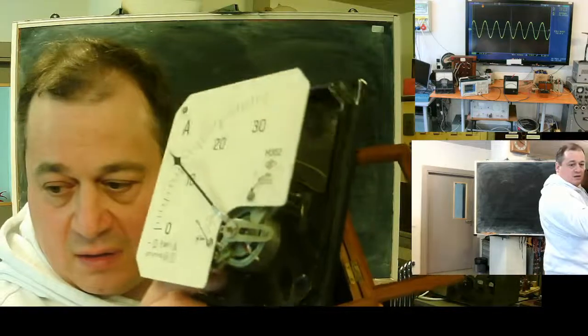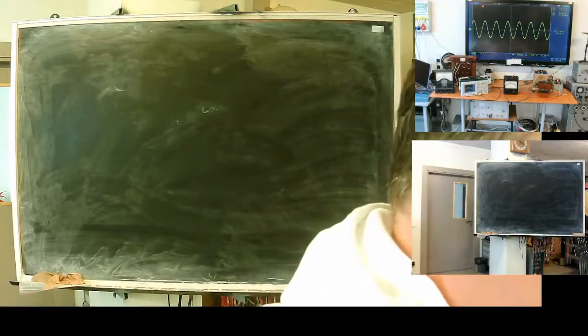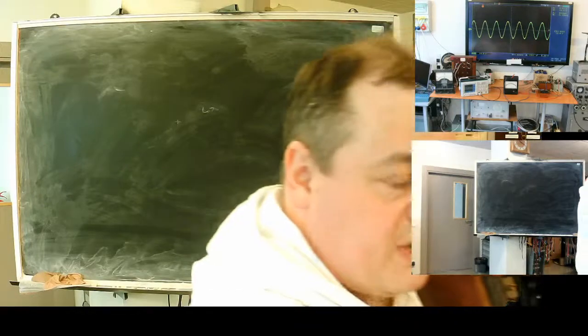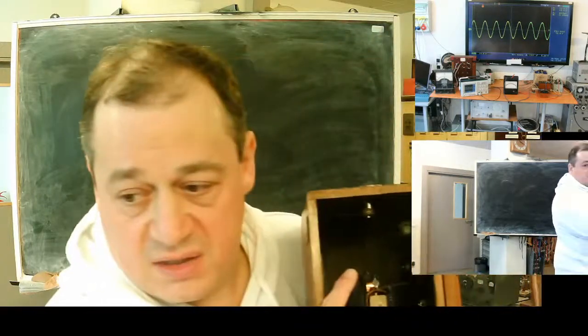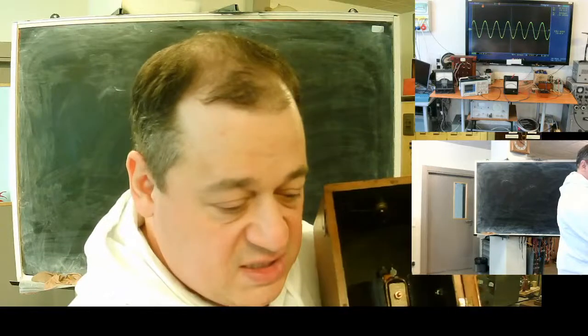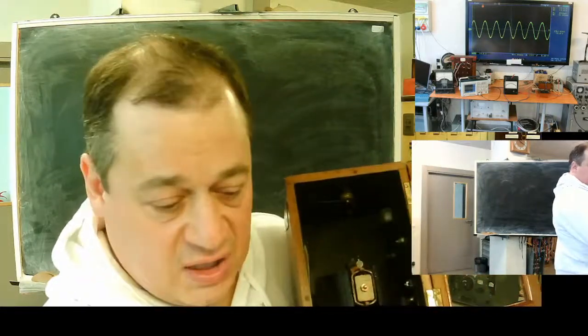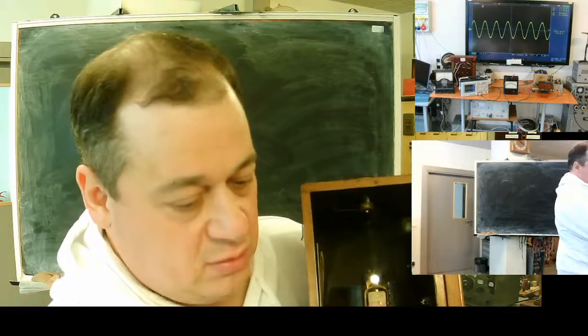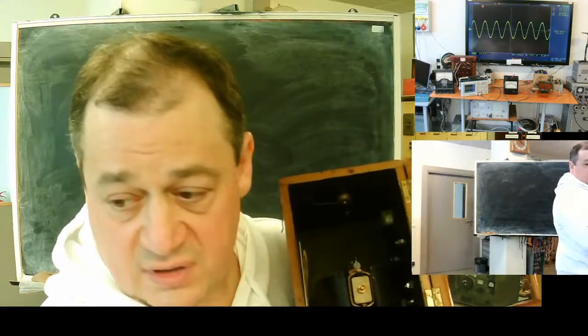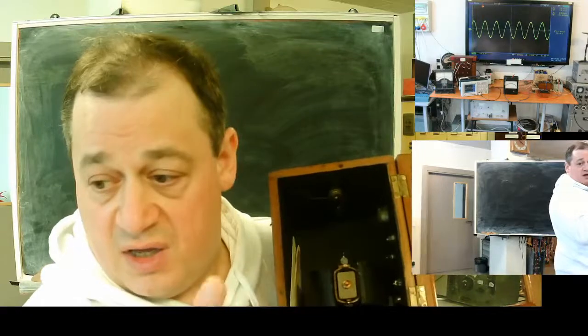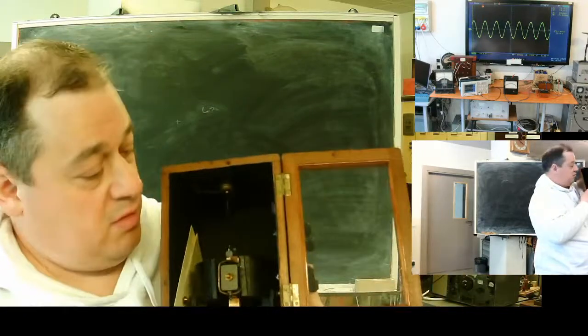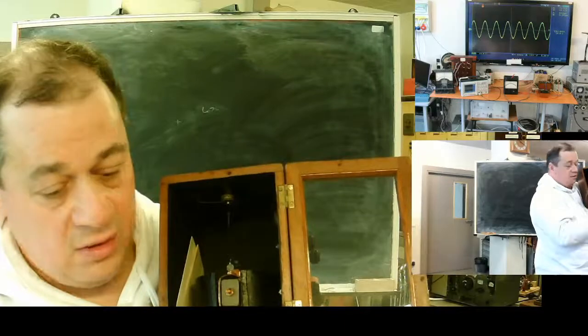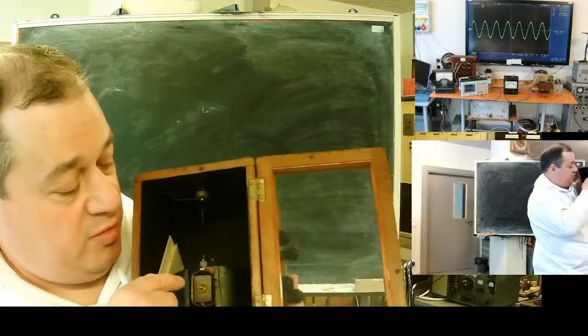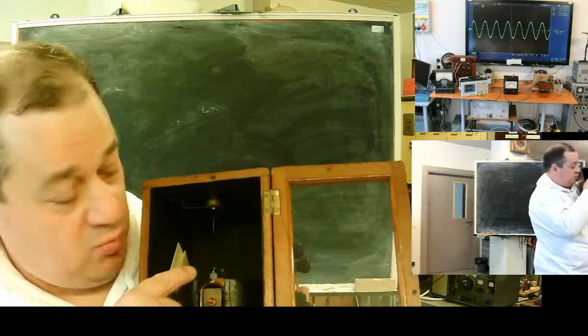And here it's the so-called Weston system. The return is provided with a kind of helix spring, here we have a flat spring. This system is more sensitive, and the deflection angle is indexed on the Weston system. With the index, a light beam was used, or laser if you have it, deflected by a small round mirror.